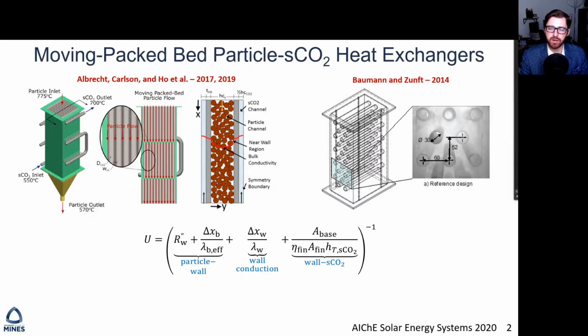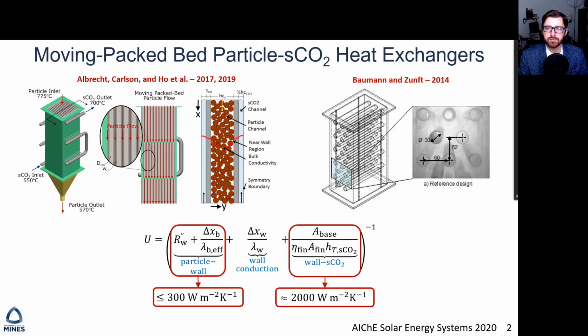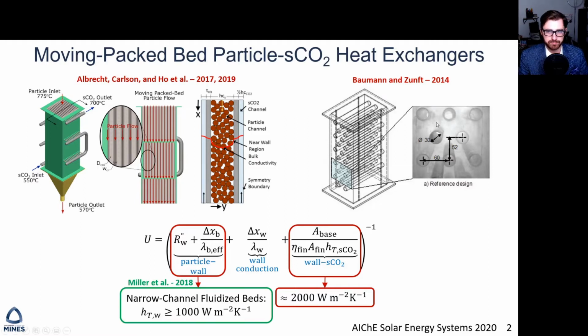Current designs for particle sCO2 heat exchangers rely on moving packed beds, where particles flow through narrow vertical channels and transfer heat to the sCO2 by sliding contact with the confining walls. While the sCO2 flow provides effective heat transfer, particle side heat transfer is limited fundamentally by the low effective thermal conductivity of the bed, resulting in effective particle wall heat transfer coefficients generally less than 300 watts per meter squared Kelvin. These designs therefore require short conduction length scales on the order of only a few millimeters and result in large heat exchangers that do not readily meet the Department of Energy cost targets for next-generation CSP plants.